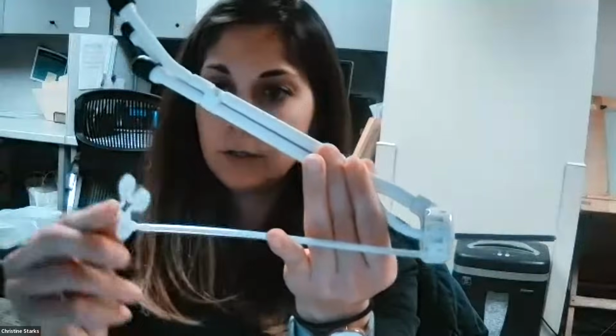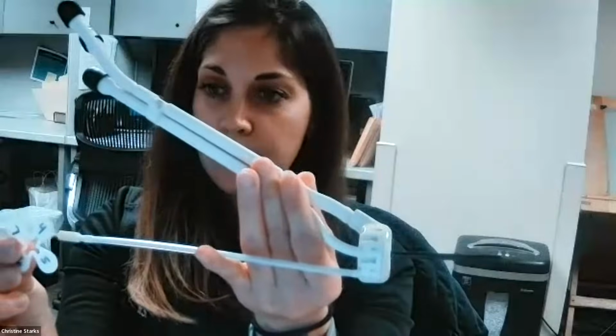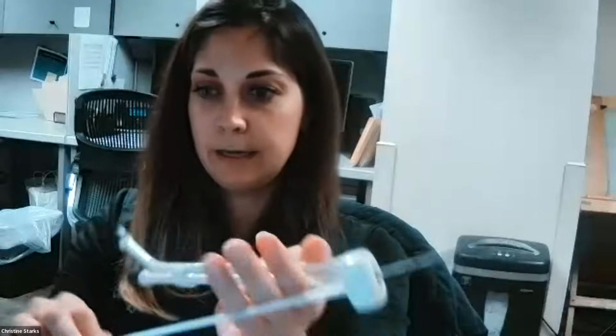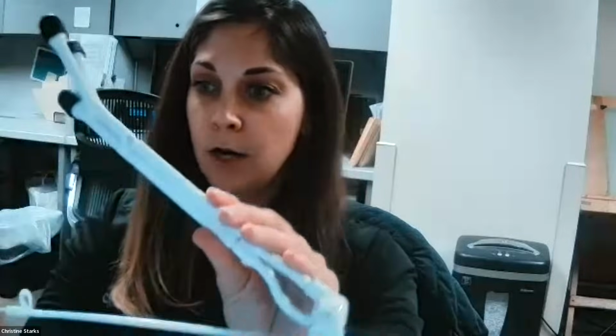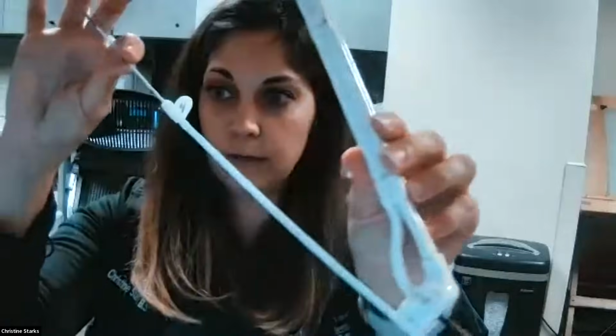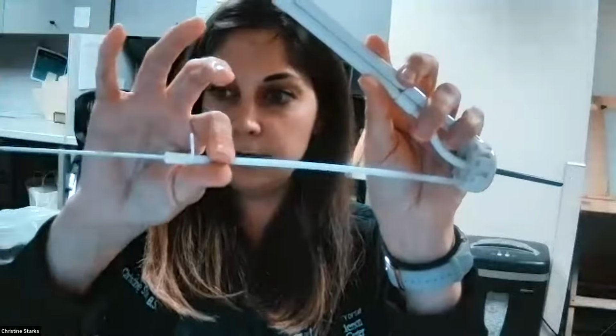we want to label the needle. Here are these little label number tags that Elekta provides, and they're really nice because you can place them right on the guide tube. It's very important to use the number tags prior to inserting the system, because once everything's inside, you won't know which guide tube is for which needle channel. You can either write the position on there, or write what catheter number you're going to choose. That's how you snap the number tags on the end of the guide tube, and that's a very important step. You can use a sterile Sharpie. I found that a Sharpie works the best for these, otherwise they'll smudge.